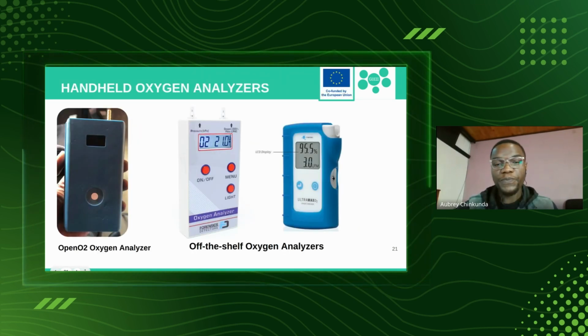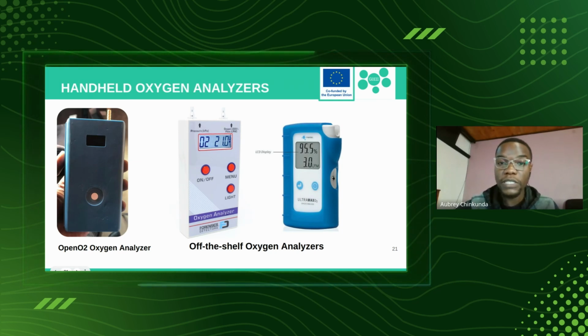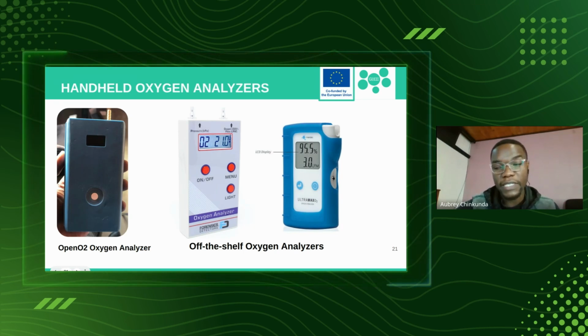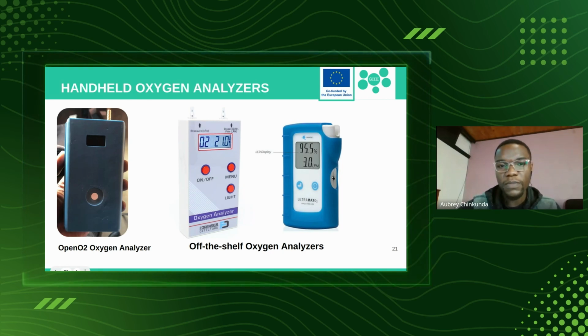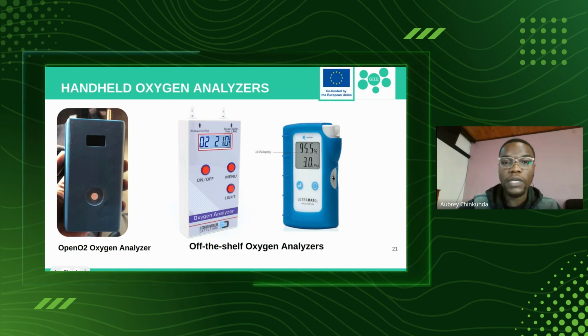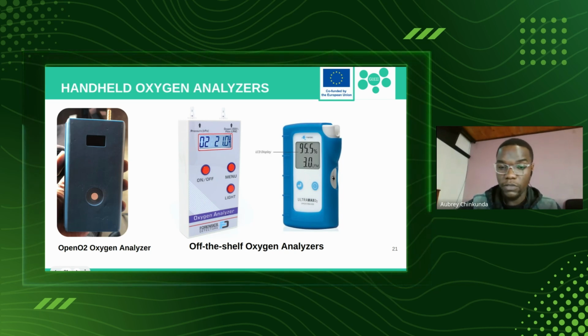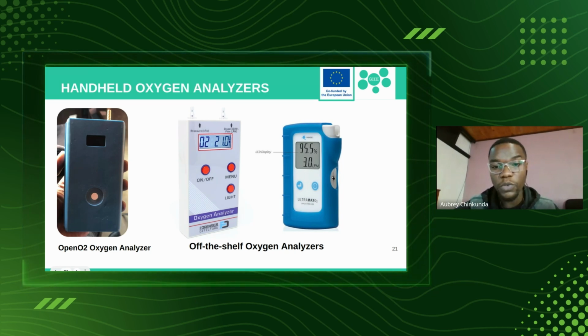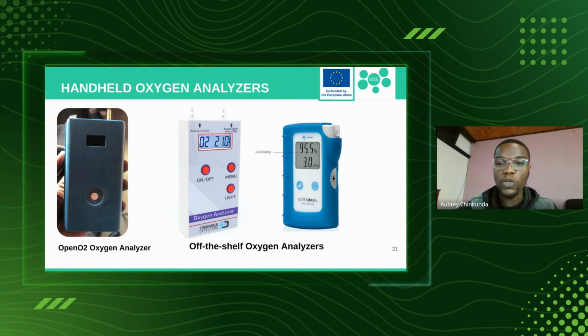After we have done the sievebed refilling, one other challenge that we have seen in most of the facilities is the unavailability of oxygen analyzers, and this was highlighted mainly during COVID time in 2021, when we had just started fixing oxygen concentrators. So we thought that one way of also dealing with this challenge is to make our own handheld oxygen analyzer. So we have one, as you can see on the far left, that's the OpenO2 oxygen analyzer. It's made at OpenO2, and we also have off-the-shelf oxygen analyzers to do some quality checks.